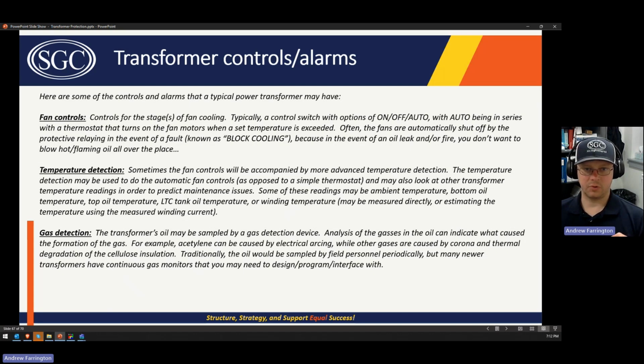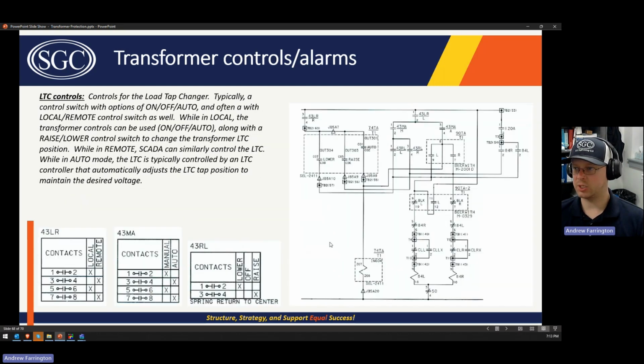Often the transformer will have some sort of maintenance schedule where they do monthly or quarterly oil samples, and they'll go to the valve at the bottom of the transformer, draw some oil, and then send it off to a lab to be tested for acetylene or other trace gases that'll tell the transformer owner if there's corona or insulation breakdown and arcing that'll cause those gases to exist in the oil, and then you'll know that the transformer is testing bad, it's failing and is in need of replacement. So that's what gas detection is.